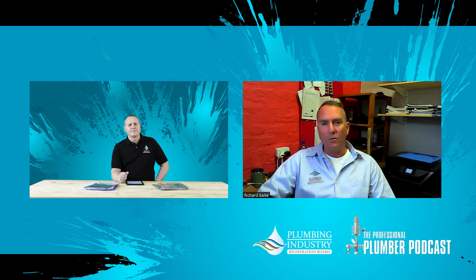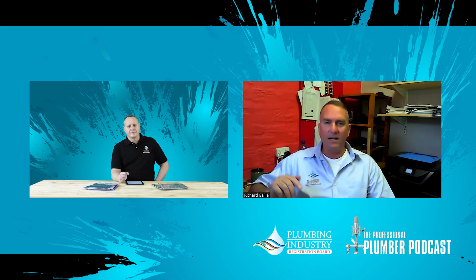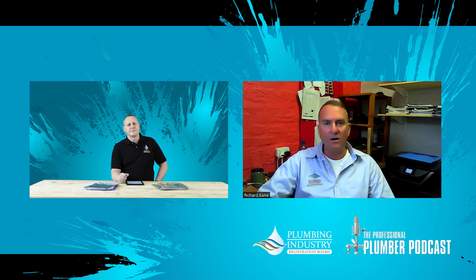So when we talk about a diffuser pipe of a heat pump system, essentially it's a simple dropper pipe which is connected to the inlet port of where the heat pump delivers its hot water to the geyser, and which drops it down to the bottom third roughly of that geyser. So that relatively cooler water is delivered actually in the bottom of the geyser rather than the top.